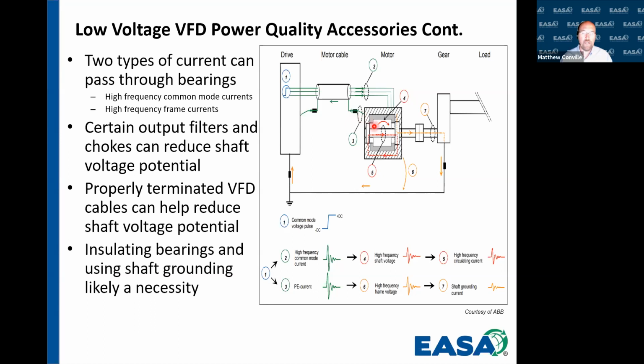When we think about shaft grounding, what you see here is if we don't have an isolated coupling, we can actually allow current to flow through the driven equipment back to earth. So if we've isolated the bearings and we put our shaft grounding brush on this end, you're going to create two problems. One, if this is not isolated, you can actually still have current go through the driven equipment. And now that we have shaft grounding on this side, you're actually going to create a difference in potential from one side of the machine to the other. So we're going to get circulating currents in the shaft as well. So you're going to create a change here, which can also be an issue for the bearings.